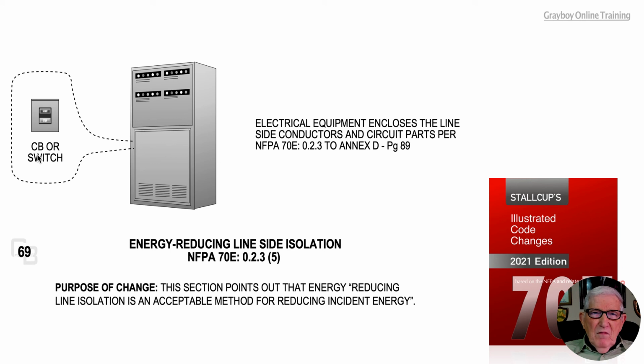Now, if we're using circuit breakers as an energy reducing type device, the NEC in 240.87, I believe around page 106, I believe it is, would list the requirements for installation. And then notice for fuses, it'd be 240.67 around page 105 of the NEC.